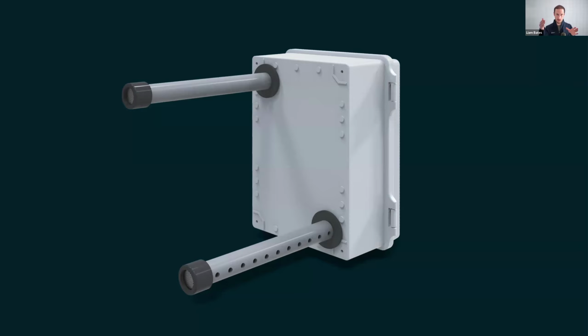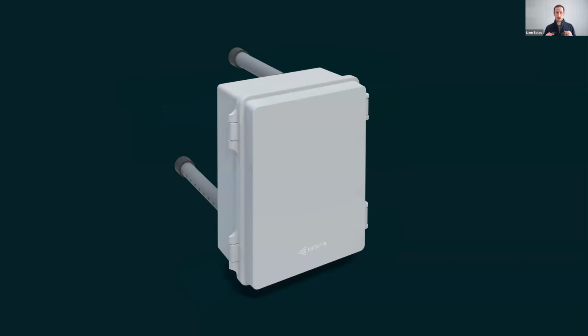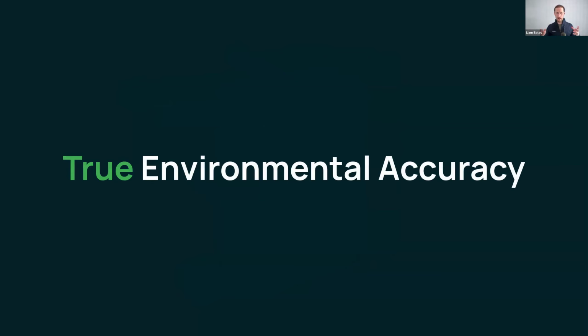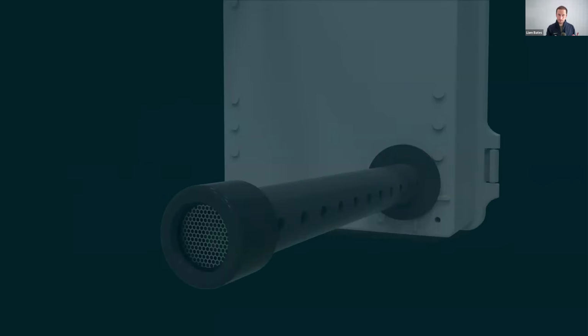So what we did is design this dual probe system that pulls air out of the duct and into this sealed sensing chamber. So that's what you see here. Now you might be asking, okay, well, if that box is sitting outside of the duct with the probes inside, how do we ensure accuracy for things like temperature and humidity, as well as some other parameters where the reading needs to reflect the actual conditions inside the duct and not in a box on the outside?